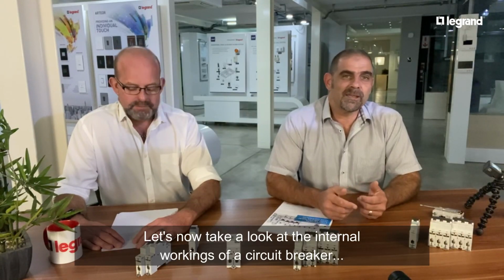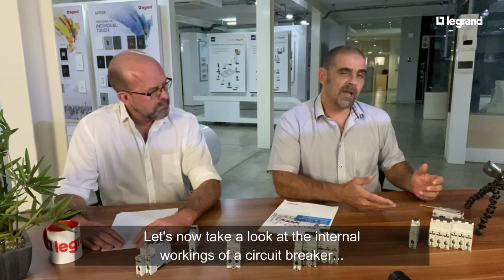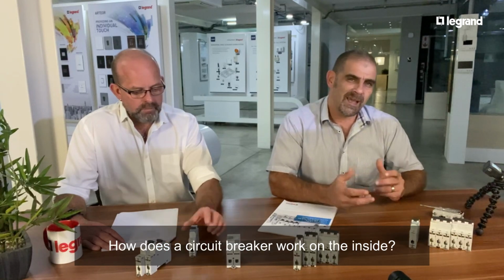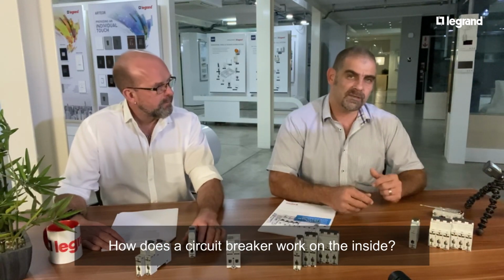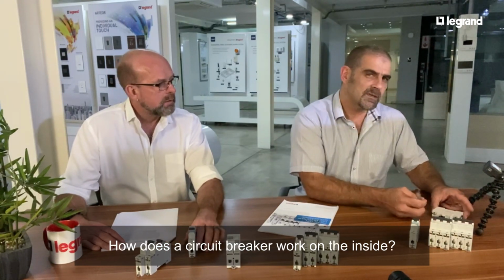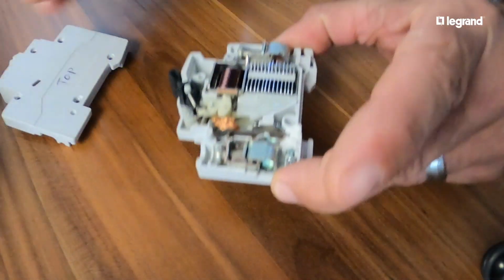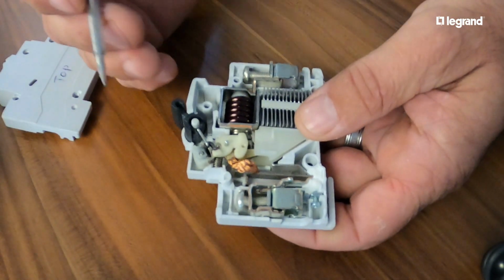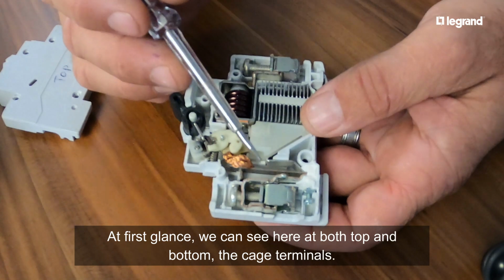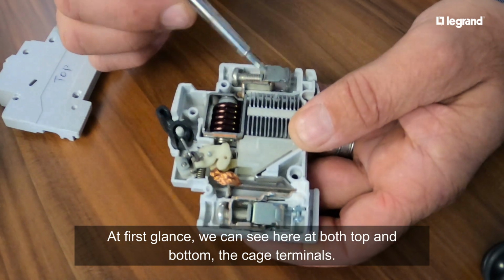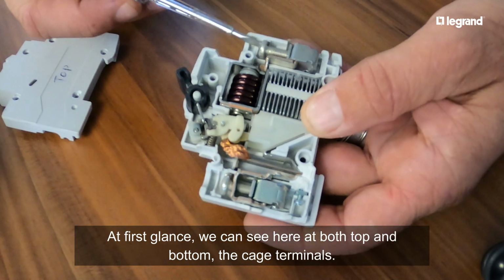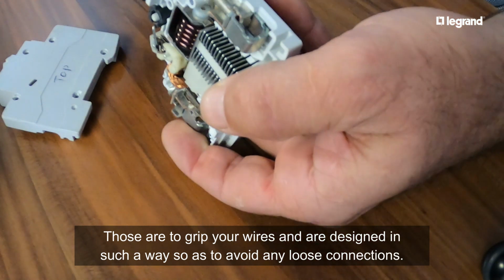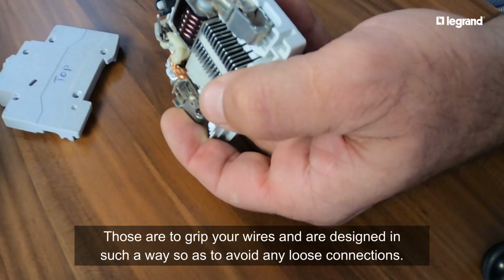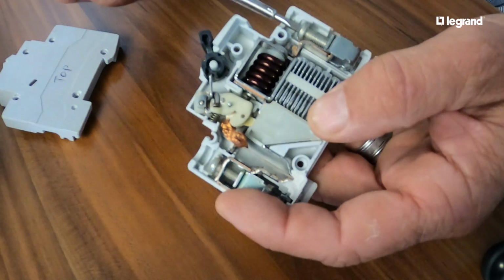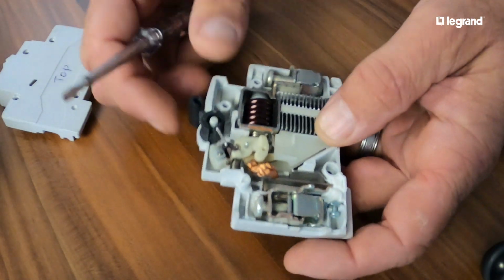I would like now to take a circuit breaker that we've opened up and show you the internal workings. How does this circuit breaker work on the inside? That's quite interesting because it's quite simple. I will explain. If you have a look on the inside at first glance, you can see the top and bottom cage terminals. Those are to grip your wires, and they are designed in such a way that, to avoid any loose connections, you can tighten them up really tight.